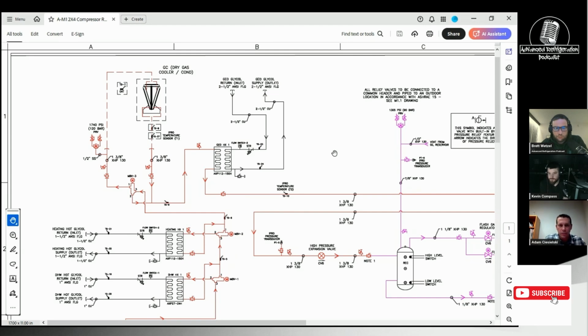But I think the bigger difference is when you start to look at a PID loop and you start to look at the band that you can control with. For example, if we look at just a proportional band, or what Copeland would consider the throttling range, for temperature, 70 to 100 degrees provides a pretty slow response. On pressure, if you look at the way pressure behaves, a throttling response of 300 does really well, but it's just a matter of what that offset is. If you're controlling head pressure, the response time for pressure compared to temperature is much faster, and it's much more controllable than it is on temperature. So preliminary results, Kevin, but what I'm seeing is very impressive to control on pressure rather than temperature.